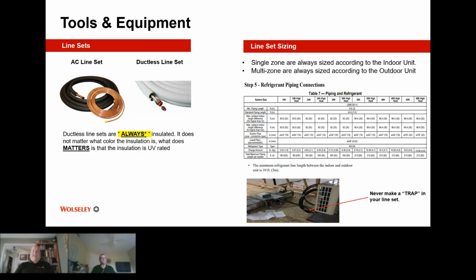And it's been my service experience that I've gone to many ductless installations and they have not used the proper Armaflex. If they ran line sets as bare copper and then put Armaflex on them afterwards, you can see, going to the job site a year later, that the Armaflex, which is not UV rated, is falling, crumbling, and basically dust in your hand when you touch it on the line set.